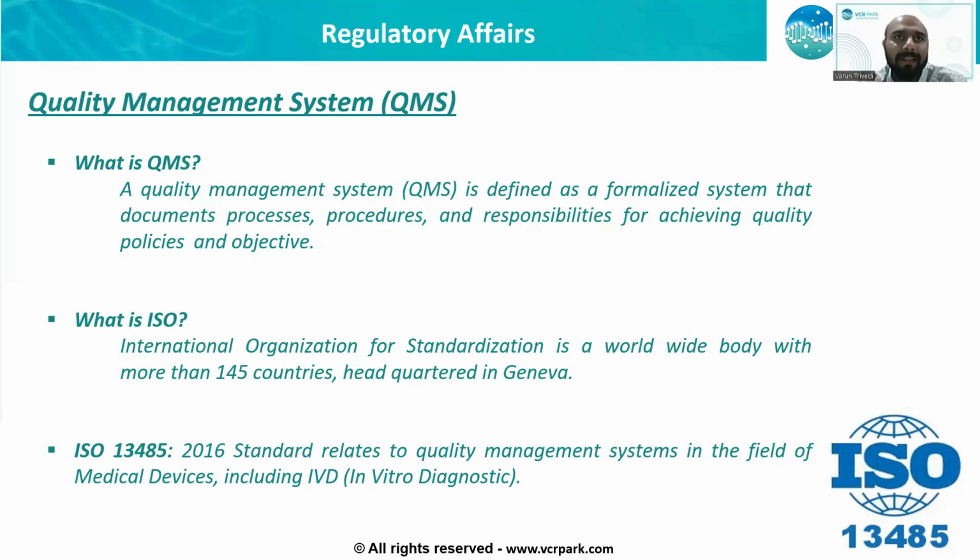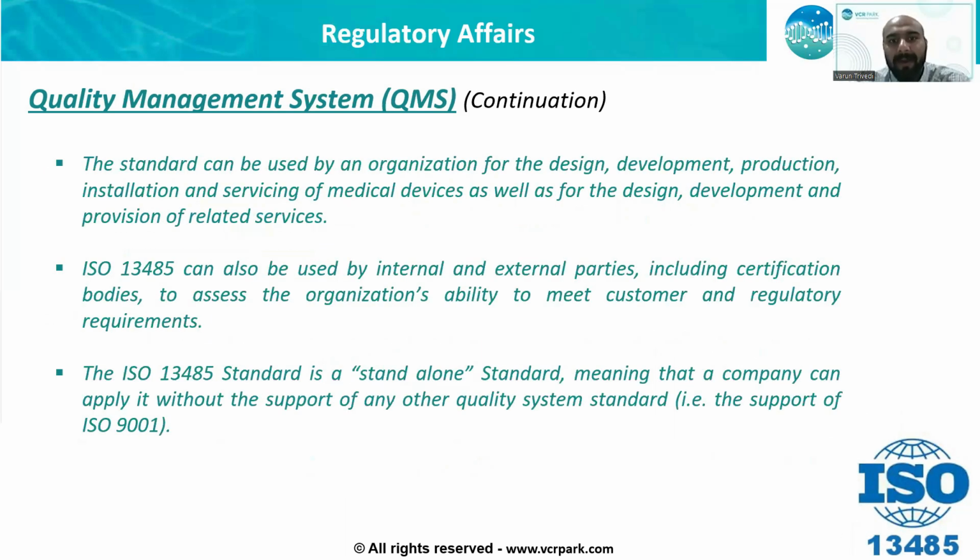Any organization that is developing any kind of medical device, may it be a general medical device, an in vitro diagnostic device, or even software as a medical device, needs to show their compliance to ISO 13485, adopting the necessary requirements of ISO 13485 and implementing them in their organization. The standard can be implemented by the organization for their design, development, production, installation, and servicing activities. This is again dependent on what are the different activities the organization carries out.